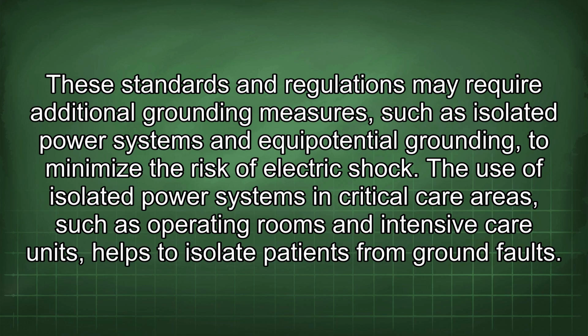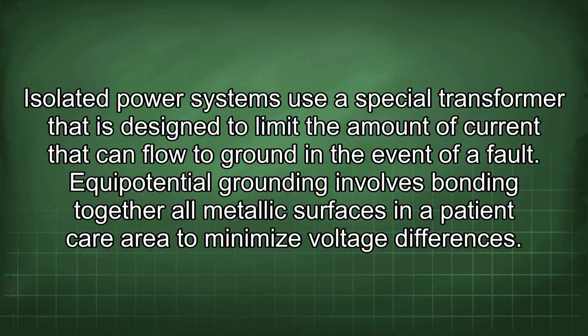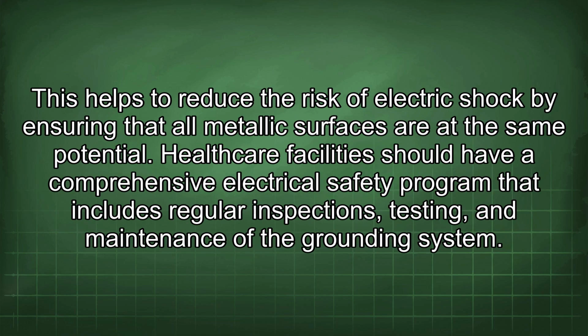The use of isolated power systems in critical care areas, such as operating rooms and intensive care units, helps to isolate patients from ground faults. Isolated power systems use a special transformer that is designed to limit the amount of current that can flow to ground in the event of a fault. Equipotential grounding involves bonding together all metallic surfaces in a patient care area to minimize voltage differences. This helps to reduce the risk of electric shock by ensuring that all metallic surfaces are at the same potential.